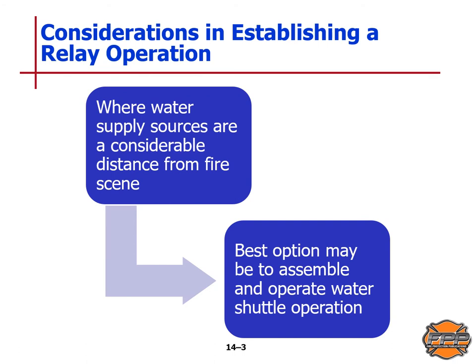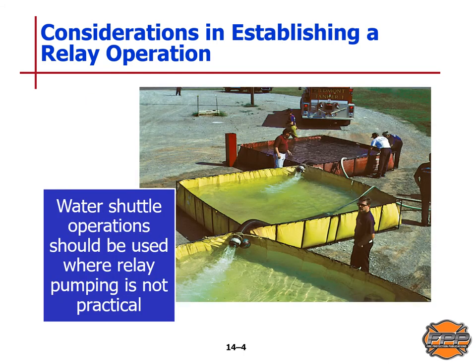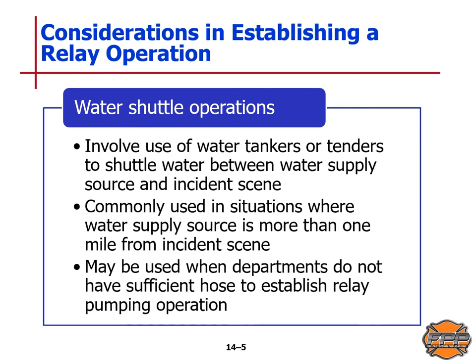Where water supply sources are a considerable distance from the fire scene, the best option may be to assemble and operate a water shuttle operation. Water shuttle operations should be used where relay pumping is not practical. They involve the use of water tankers or tenders to shuttle water between water supply sources and the incident scene. These are commonly used in situations where the water supply source is more than one mile from the incident area, or may be used when departments do not have sufficient hose to establish a relay pumping operation.